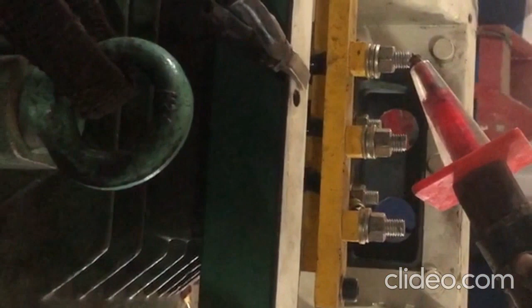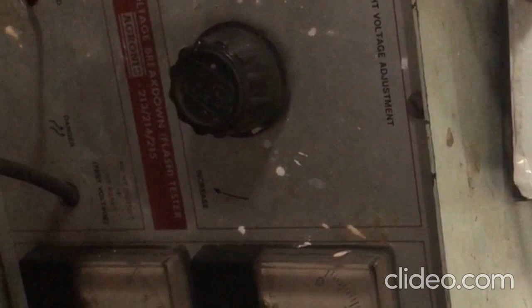Hold it for 30 seconds. Leakage current has to build. Let's see, the leakage current does not fluctuate, nor does it build. It's steady at 2 kV, phase to ground.